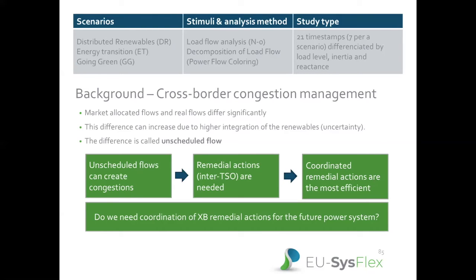But the rest of the flows can fit into thermal capacity or can exceed it, causing the network congestions. And if we approach congestions, then we have to go into remedial actions, which are mainly redispatch, using of phase shifting transformers, topology switching, and so on. And we claim that coordinated remedial actions are the most efficient. So now we can ask the most important questions here. In fact, how great is the magnitude of envisaged unscheduled flows? Do we expect some substantial need for cross-border coordination in the future, especially in the context of high penetration of renewables? And would we encounter any technical scarcities in terms of cross-border coordination? And this research was conducted based on the data introduced by PSC Innovation.